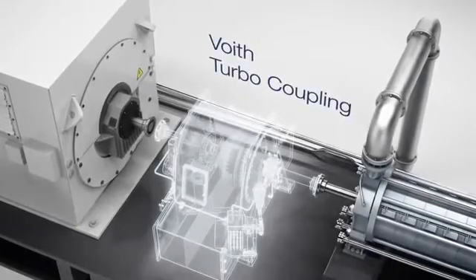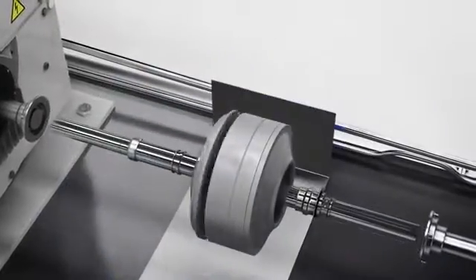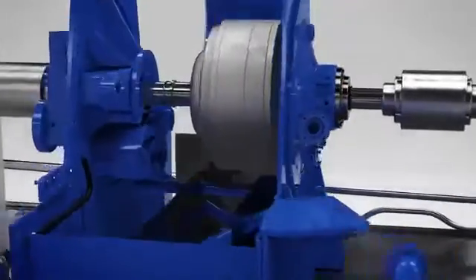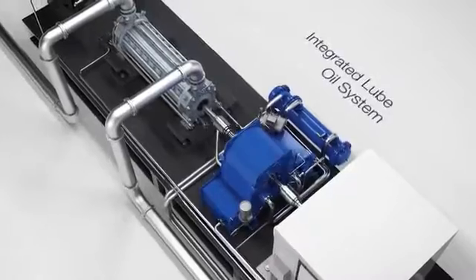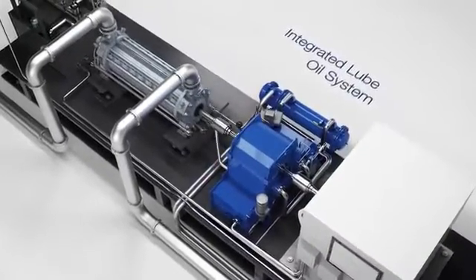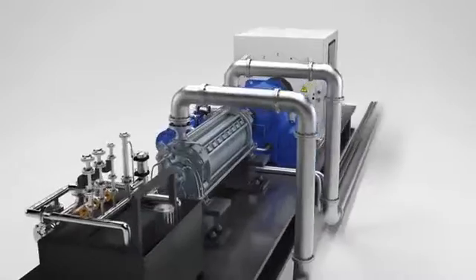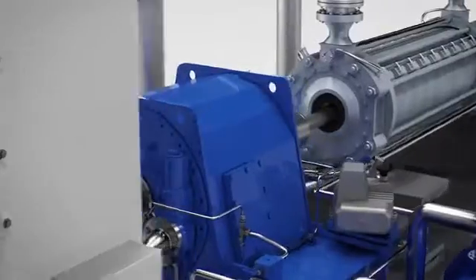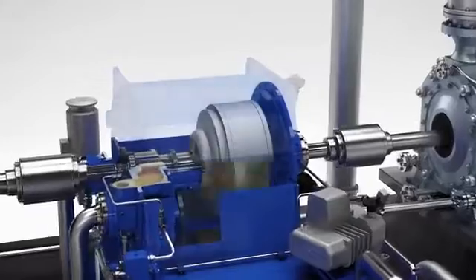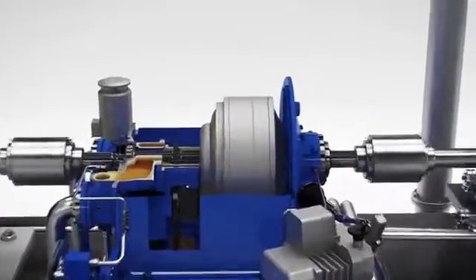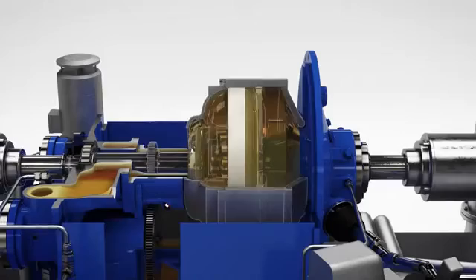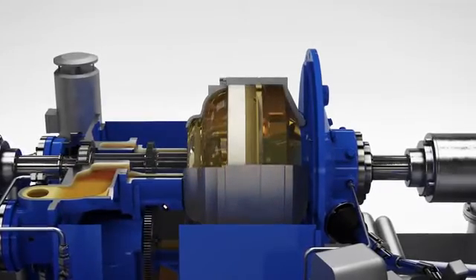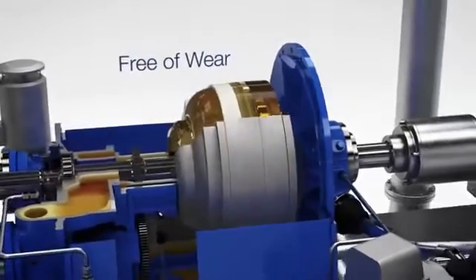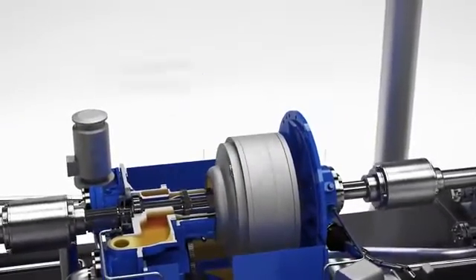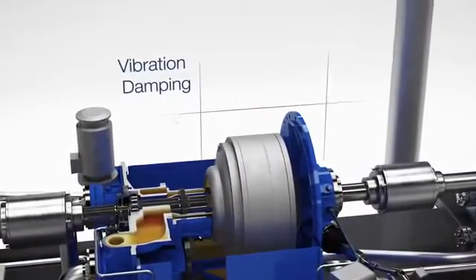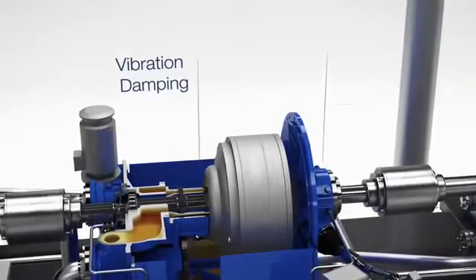Controlling pump speed using Voith hydrodynamic couplings, which feature outstanding energy savings and high reliability, is a significantly more economical solution. The hydrodynamic coupling's integrated oil system supplies the bearings of the boiler feed pump and the electric motor with lubricating oil. A separate lube oil supply system is now no longer necessary. The principle of hydrodynamics is based on using oil to transfer the power coming from the motor. There is no mechanical connection between the motor and the driven machine. This ensures a wear-free power transmission. At the same time, the oil serves as a damping medium, filtering out torsional vibrations and torque peaks. This increases the service life of the entire driveline.